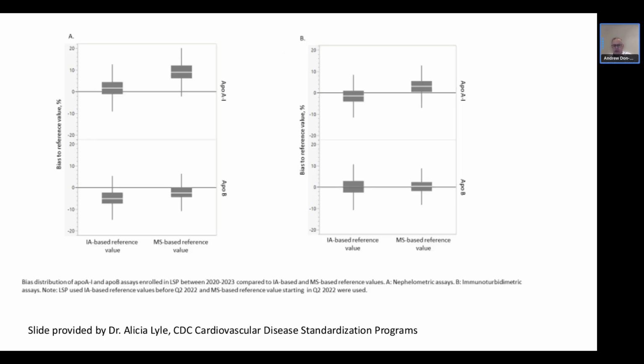So Dr. Alicia Lyle from the CDC did provide me with this slide. She gave a presentation at the ADLM meeting where she'd gone through some of this data in more detail, and part of the presentation had ApoB in it, so I'd asked her for an updated slide. The lipid standardization program at the CDC has moved from an immunoassay-based reference value for apolipoprotein B to a mass spec-based reference value, and I'll discuss that on my next slide in a little bit more detail.